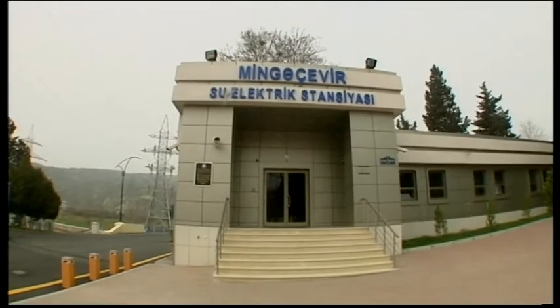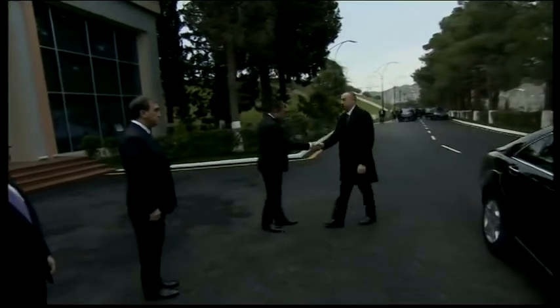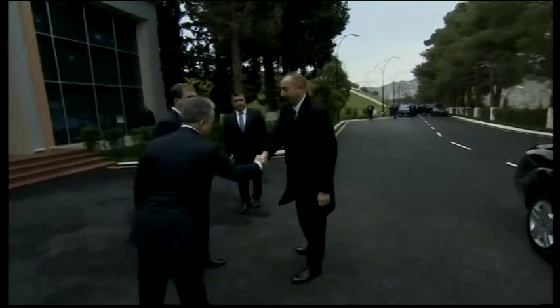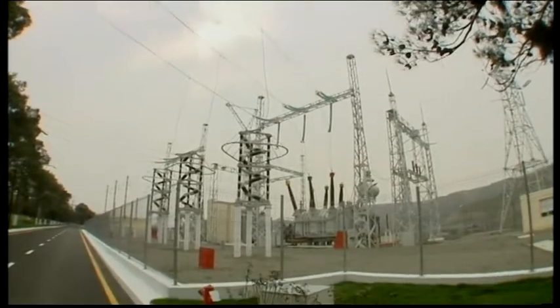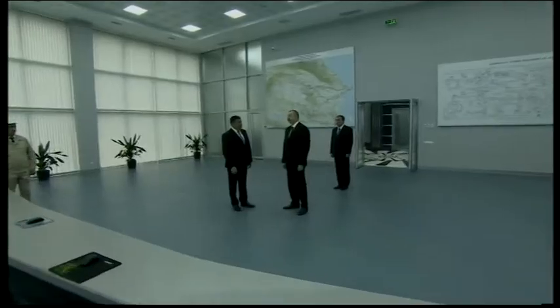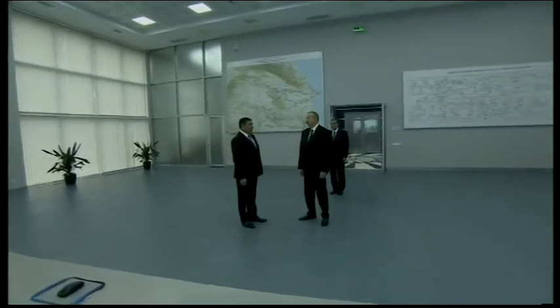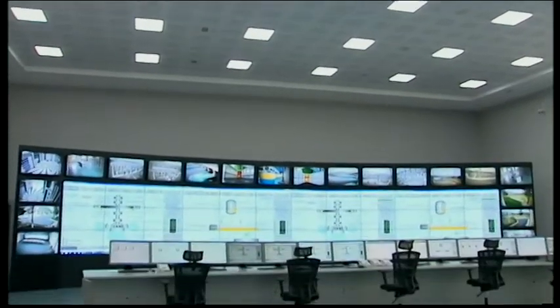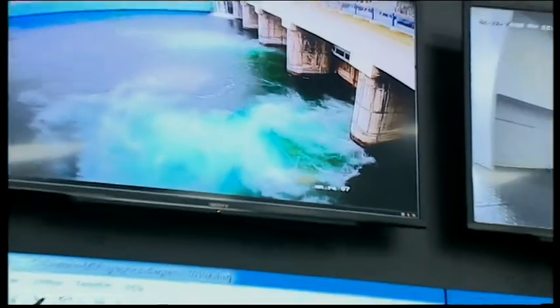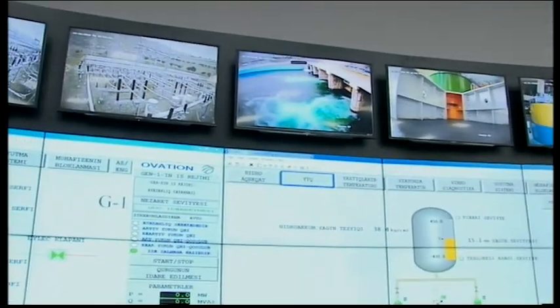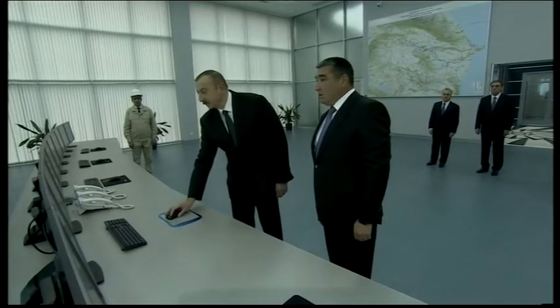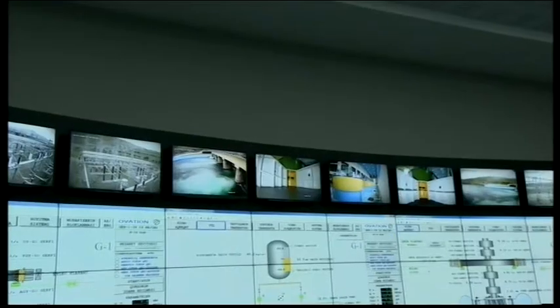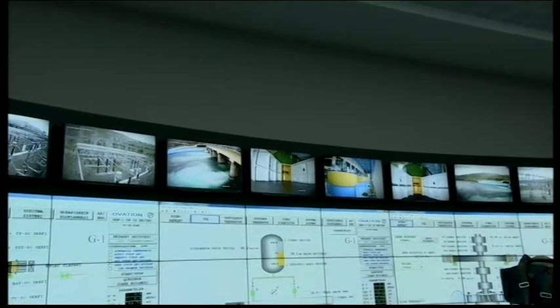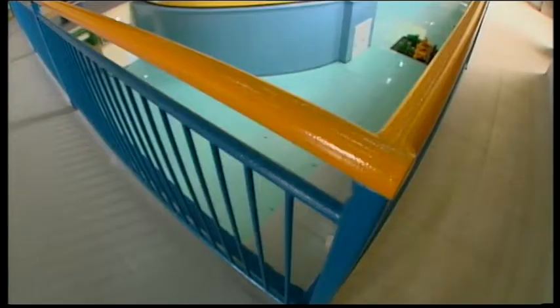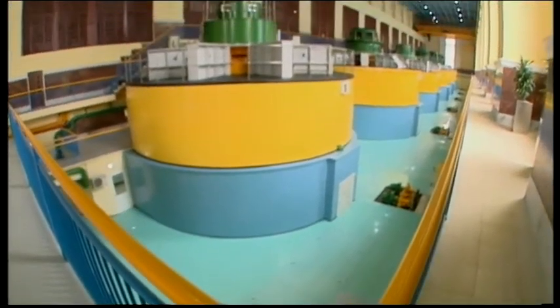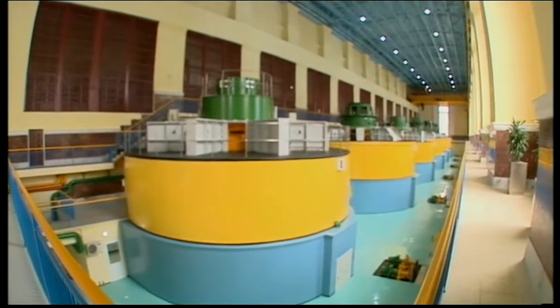The head of state took part in the opening ceremony of the Mingachevir hydroelectric power plant with a capacity of 424 megawatts after the major overhaul. President of Azerenergy Open Joint Stock Company Tabar Pirverdiev informed the head of state that in 2010-2017 the control center was reconstructed in accordance with modern requirements and the energy system was coordinated with the central management system. Turbines and generators with a capacity of 71.5 megawatts have been installed, and new substations have been commissioned. As a result, the station's capacity was increased from 284 to 424 megawatts.